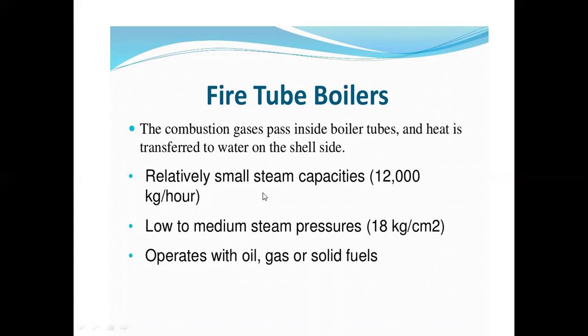Fire tube boilers are used for relatively small steam capacity, that means up to 12,000 kg per hour, and for low to medium steam pressures. That means up to 18 kg per square centimeter, and maximum up to 25 bar of pressure. For that application we use fire tube boilers.